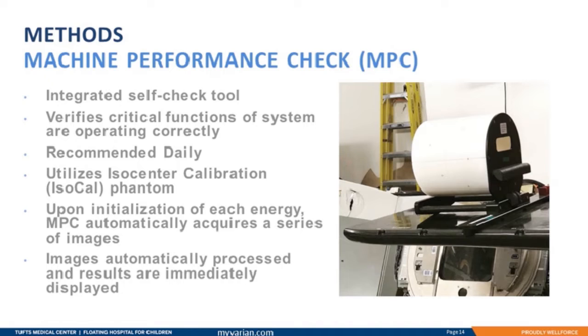Once this is done, Machine Performance Check automatically drives the Phantom to the correct position and then automatically acquires a series of MV and KV images per energy, capturing beam properties as well as mechanical characteristics for different collimator and gantry rotations, couch settings, and collimating devices. The acquired series of images is immediately processed and the results displayed to the user for quick evaluation.